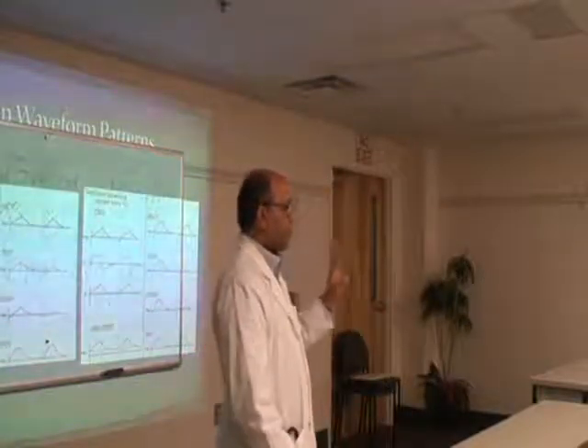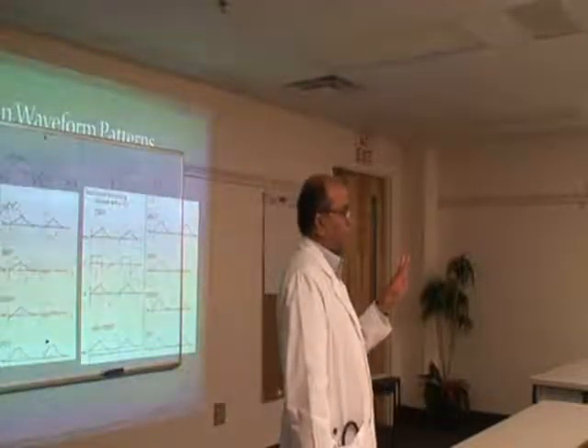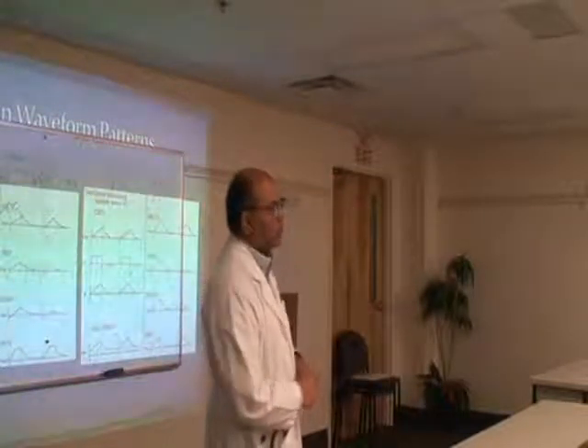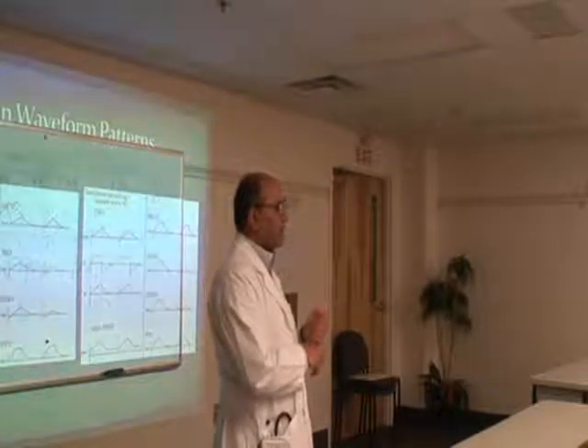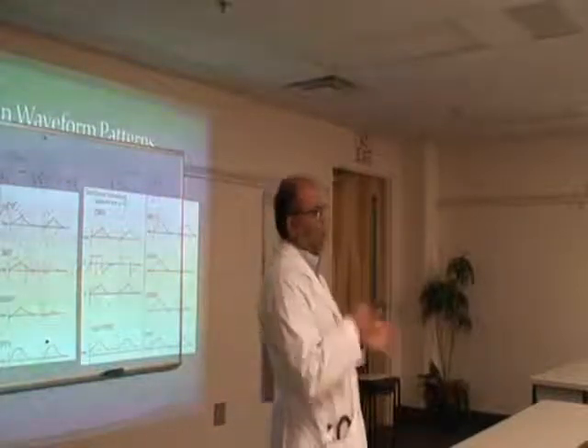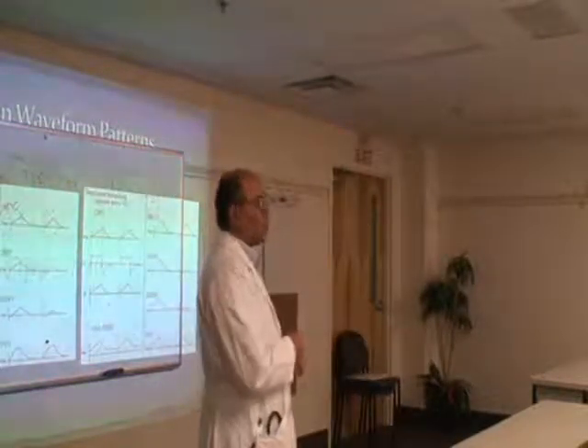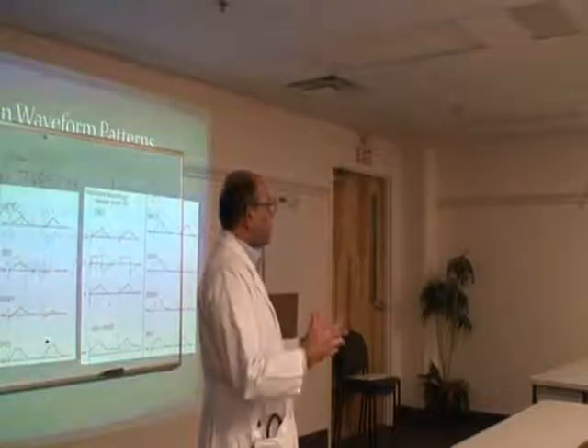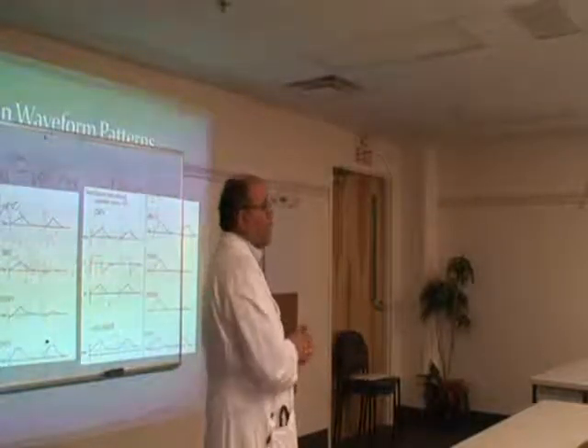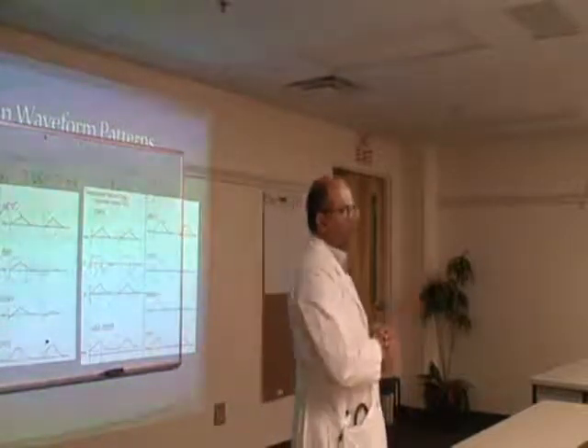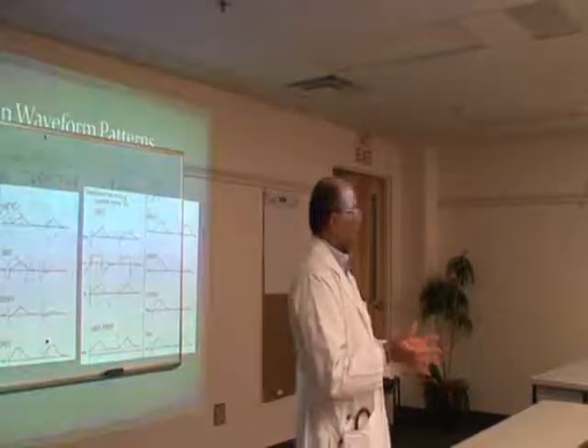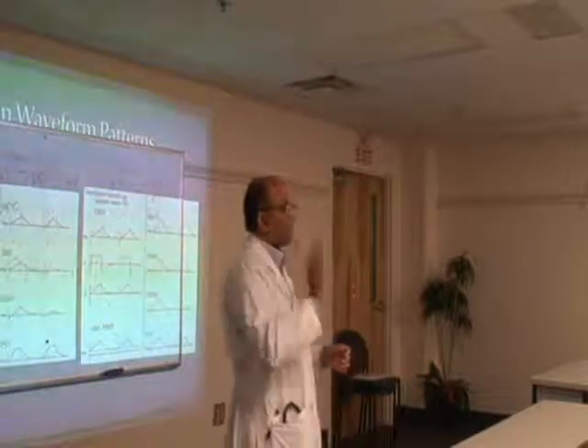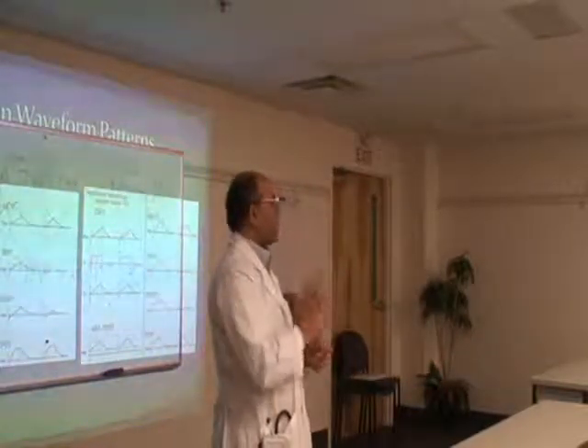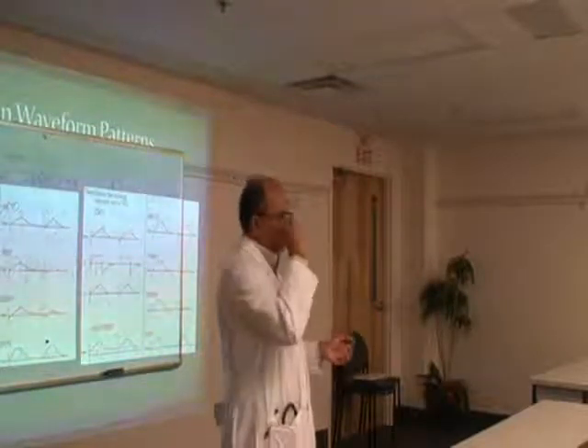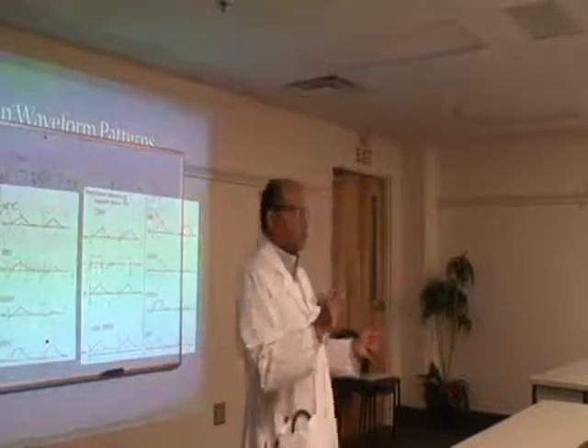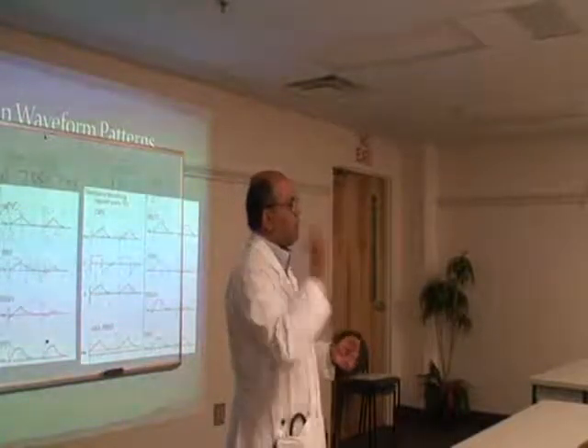With bi-level, you have 3 settings. The first that we'll do is a rate. Like on a ventilator, we're going to put them on a rate. The rate is how many breaths that machine is going to give to that patient on top of whatever he might do on his own. So if the patient's breathing 20 and you have a rate of 12, it doesn't mean he's going to breathe 32 now. But the machine will give him a minimum of 12 breaths per minute, one every 5 seconds.